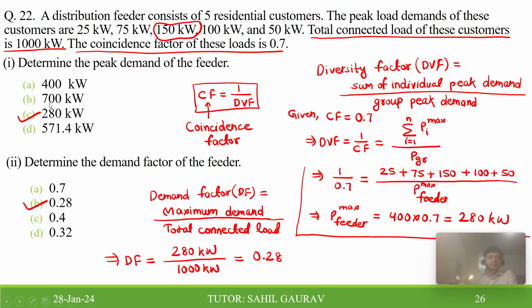This is 280 kilowatt. Yes, it may come, it may increase to 300, 350. It may happen practically. Based on this data you can say what it will be. So the maximum demand can be increased if you change this coincidence factor.